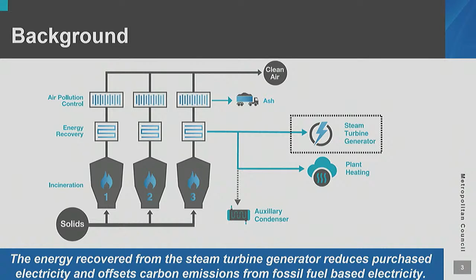Some background: the Metro Plant uses 3 fluidized bed incinerators to treat our wastewater solids, collected from the liquids treatment system. Heat energy is recovered via hot exhaust gas by the waste heat boilers. The waste heat boiler produces steam to heat plant buildings or generate electricity in a steam turbine generator. Excess steam can also be sent to the auxiliary cooler or condenser. The equipment we're here to discuss is the G7 steam turbine, shown in the dotted box to the right. The G7 steam turbine generator is located in the solids management building at the Metro Plant, and the power it produces is used on-site, reducing our purchased electricity and offsetting carbon emissions from fossil fuel-based electricity.